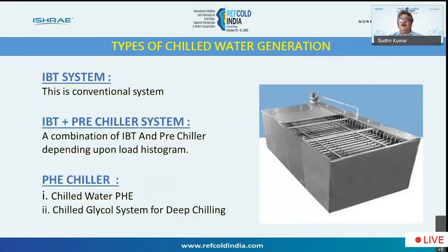Okay, now we come to the types of chilled water generation. What are the types of chilled water generation? There are 3 types of chilled water generation. One is the conventional IBT system. In the earlier days, the dairy plant used to have only IBT system. And this IBT system used to work at minus 10 degrees, and it was a very foolproof system. People used to have IBT system so that in case there is a power cut or power failure, you still have ice stored in your ice bank tank.